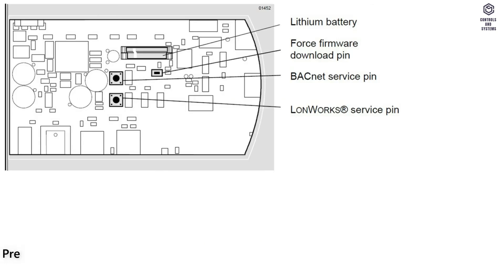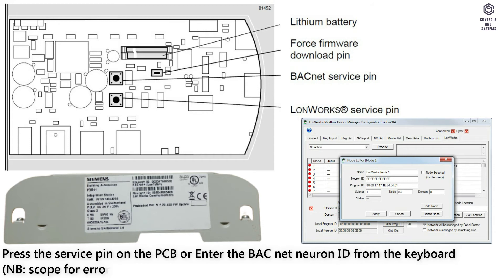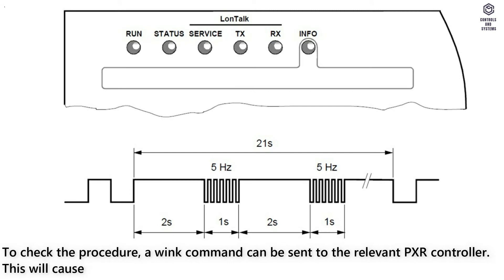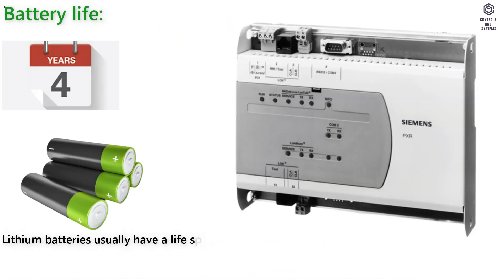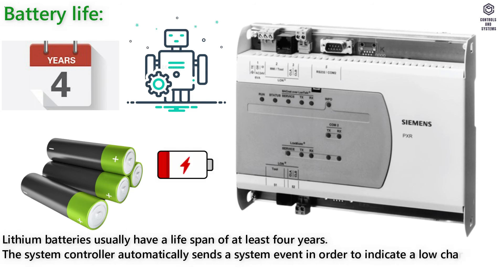Addressing: press the service pin on the PCB or enter the BACnet neuron ID from the keyboard. To check the procedure, a wink command can be sent to the relevant PXR controller; this will cause the associated service LED to flash for 21 seconds. Battery life: lithium batteries usually have a lifespan of at least 4 years. The system controller automatically sends a system event to indicate a low charge.